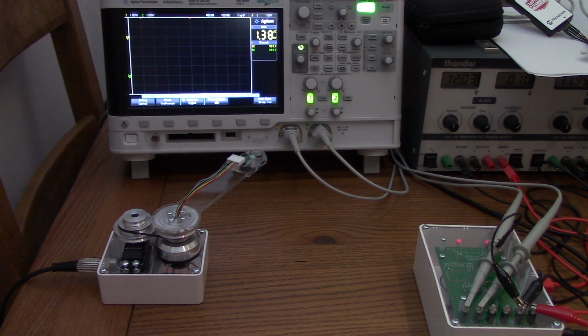So I'm going to take option 2 and change the gain value K, which now becomes Ku, to 2, and remember this is for a 1-to-1 ratio. And the time constant, I'm going to change by selecting option 3, the integration time constant, which in this case is 0.296 seconds, or in the HMI it's in milliseconds, so we're going to enter 296.